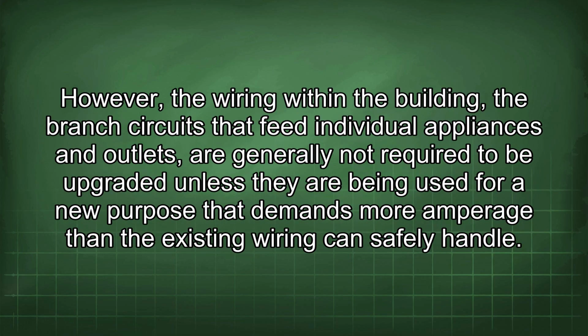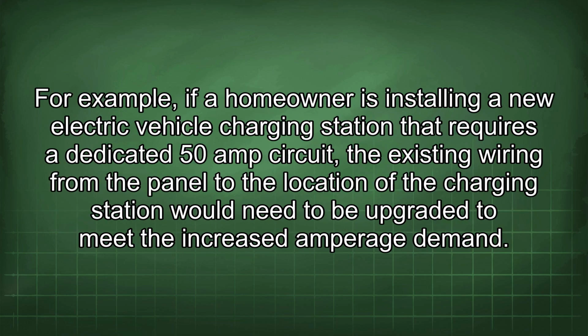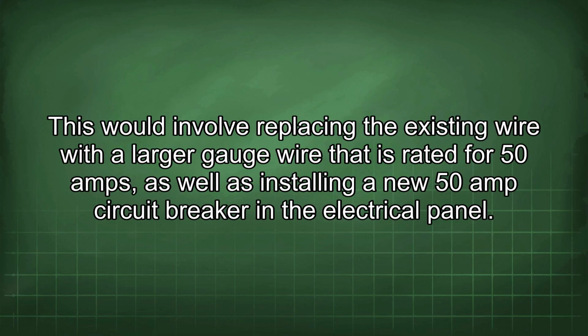However, the wiring within the building, the branch circuits that feed individual appliances and outlets, are generally not required to be upgraded unless they are being used for a new purpose that demands more amperage than the existing wiring can safely handle. For example, if a homeowner is installing a new electric vehicle charging station that requires a dedicated 50 amp circuit, the existing wiring from the panel to the location of the charging station would need to be upgraded to meet the increased amperage demand. This would involve replacing the existing wire with a larger gauge wire that is rated for 50 amps, as well as installing a new 50 amp circuit breaker in the electrical panel.